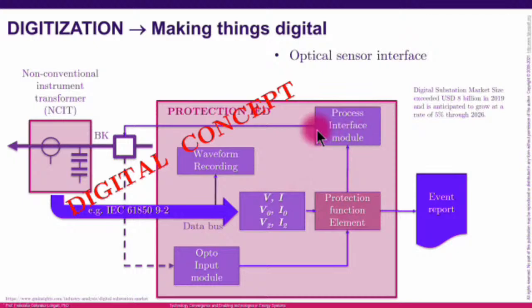In this digital concept, the trip signal can also be a digital signal. In that case, we are using a very specific part of IEC 61850, the GOOSE messaging, in order to order the trip of the power circuit. And here, when I say we are sending data strings with packets related to voltage and current using 61850, I am talking about one very specific section of the protocol that is for sample values.